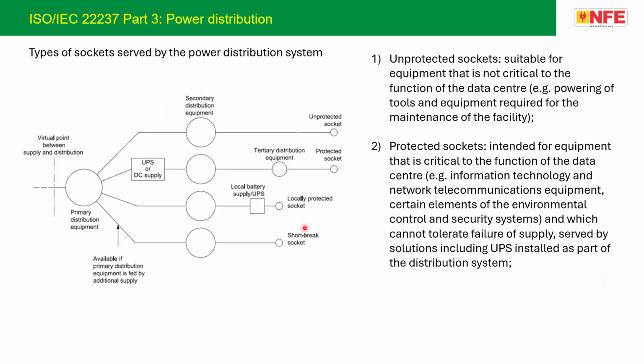Now, the sockets. Finally, the equipment are connected to the final point, which is the socket. There are 4 types of sockets defined in the standard: unprotected socket, protected socket, locally protected, and short break socket. Unprotected means it is suitable for equipment that is not critical to the functioning of the data center. Example, powering of tools and equipment required for the maintenance of the facility. Protected socket is for the data equipment, intended for equipment that is critical to the function of the data center. Example, information technology and network telecommunication equipment, certain elements of environmental control and security system, and which cannot tolerate failure of supply.